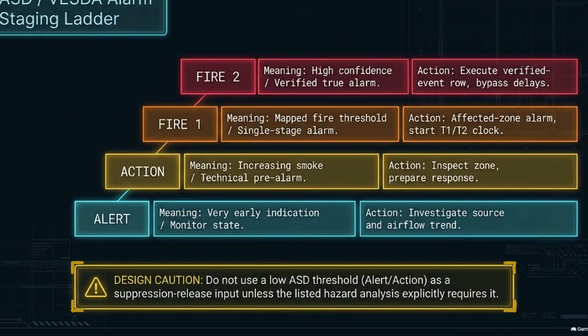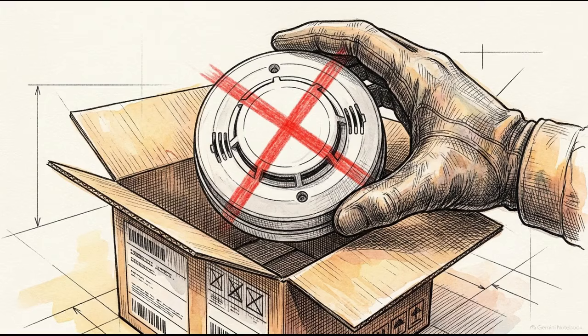The design rule is uncompromising. A low ASD threshold can never be used as a suppression release input unless the approved hazard analysis explicitly requires it. A facility's detection strategy cannot rely on default device sensitivities out of the box. It must be engineered to match the exact thermal and velocity physics of the protected space.